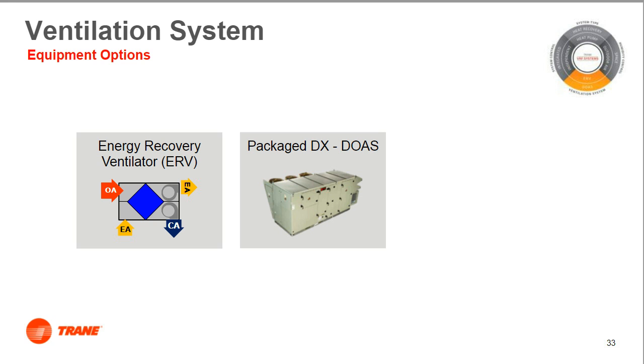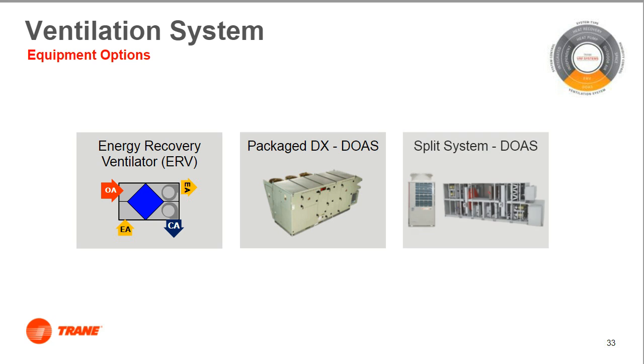So it's important to note that equipment conditioning the outdoor air also affects space humidity. An ERV provides passive cooling and dehumidification, while a dedicated outdoor air system provides active conditioning. Said another way, the ERV does what it can, but is constrained by the ambient conditions and air-to-air energy recovery device, while the dedicated outdoor air system actively conditions to a specific defined set point using cooling and heating coils.